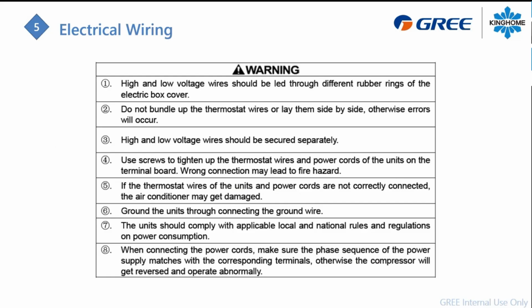So just a little bit of security things here. Make sure everything is connected properly. Your high and low voltage wires should be led through different rubber rings. Make sure you don't bundle the thermostat wire, to not create some kind of error. High and low voltage must be separate, and make sure the wire is held properly. Sometimes you can add some clips to hold the wire correctly.